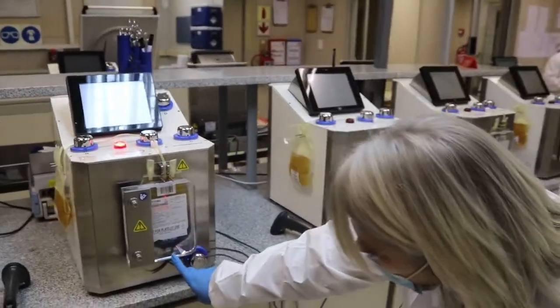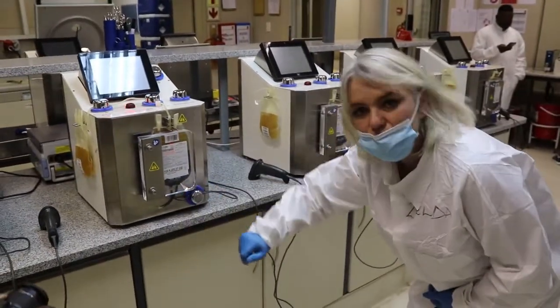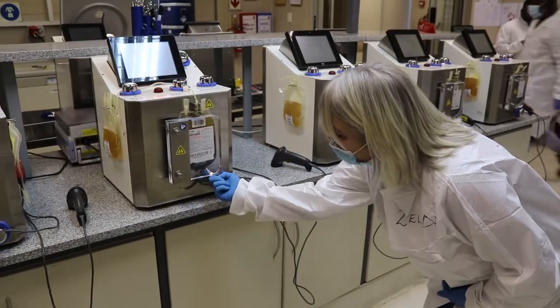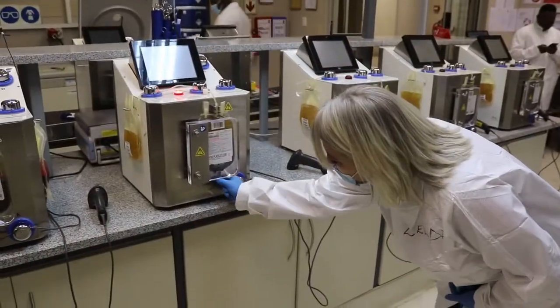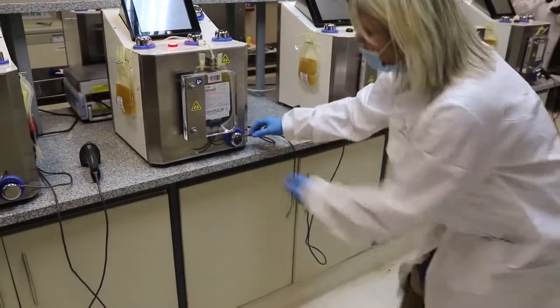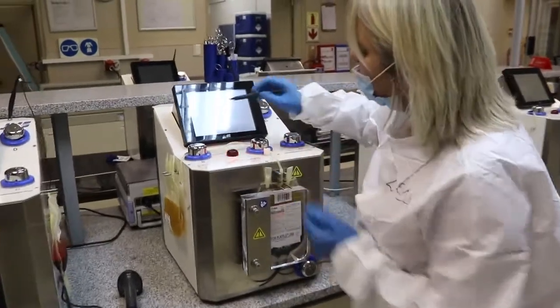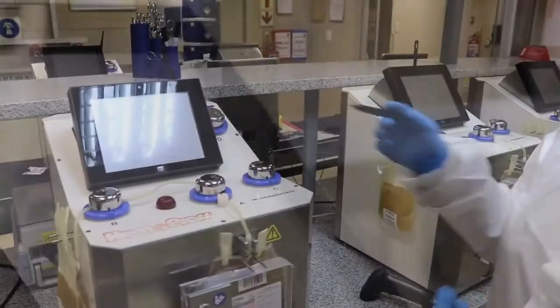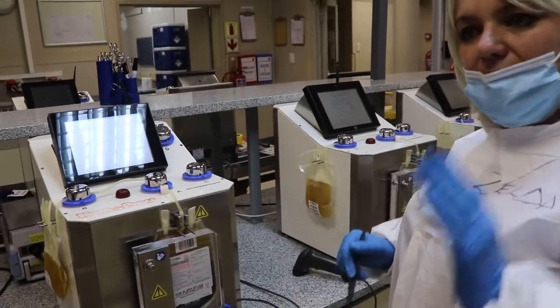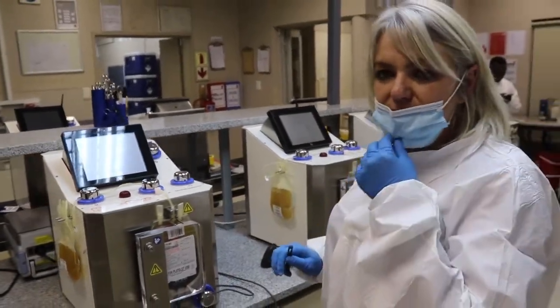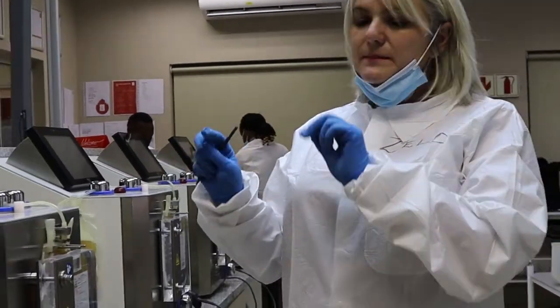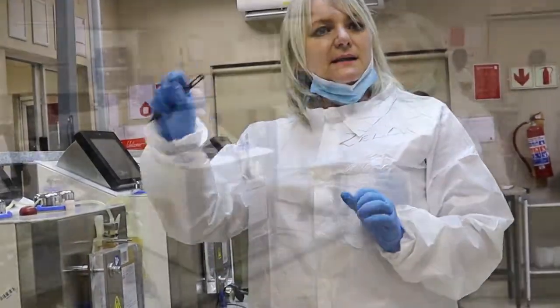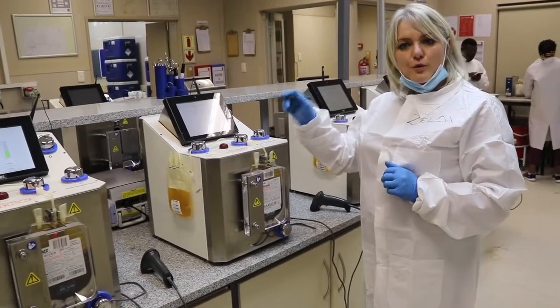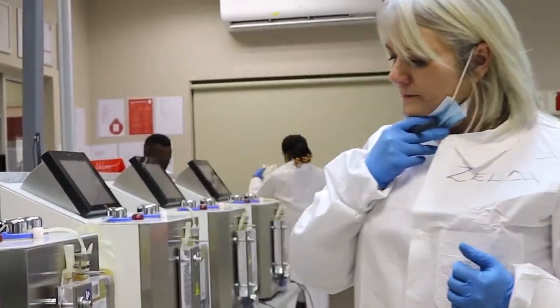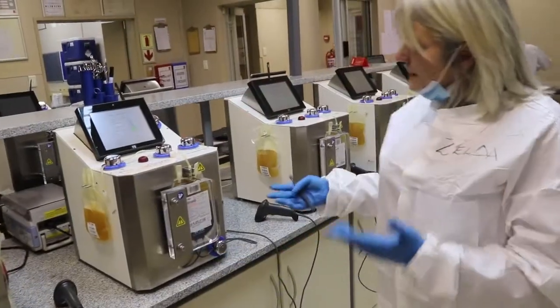Second thing, when we load the bag onto the machine, it's bent in at the bottom. So you just pull it out, check the clamp is open, continue process, and we say yes. And our processing will continue. So anything that could go wrong during a process, to save a unit, it will immediately seal your tubing and give you an alarm to indicate what your problem is during this process. So now that we've straightened this, everything's going fine.